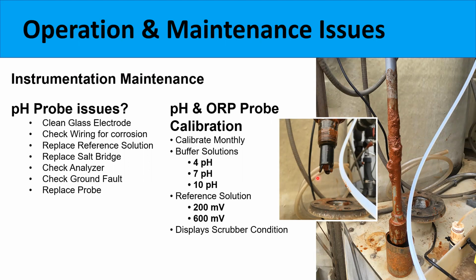You can also have some other issues that crop up with pH probes. We've seen ground fault issues, especially in situations where a VFD-driven fan, a fan that's operated by a variable frequency drive, is in the area and causing a little bit of resonant noise and stray current if that sump is not grounded properly, because of those very sensitive electronics in those pH probes. So there are a couple of things there you can troubleshoot.